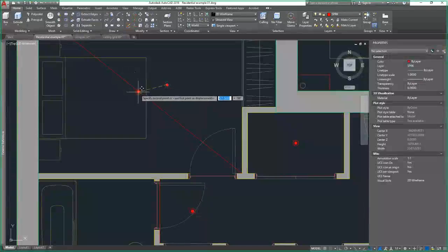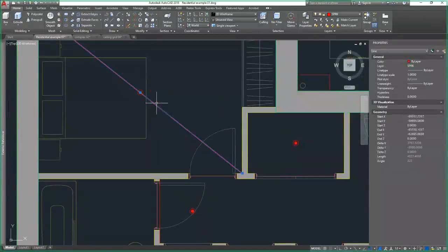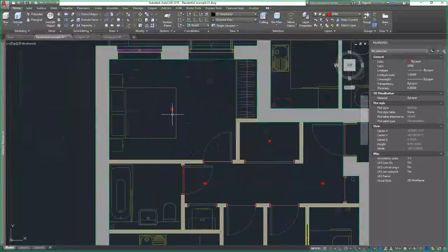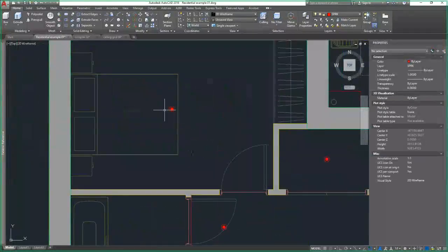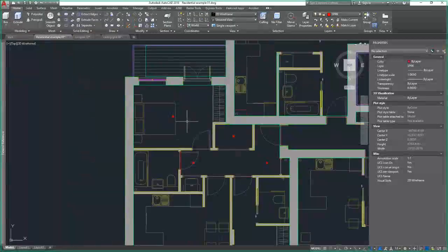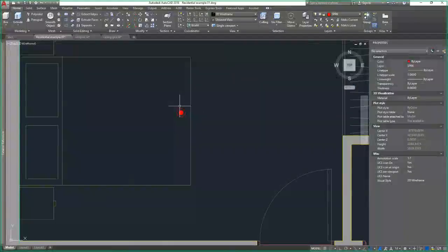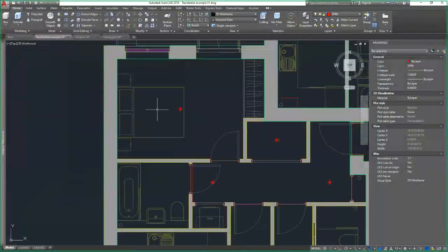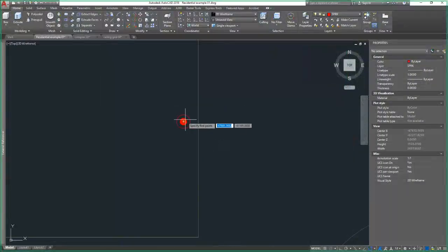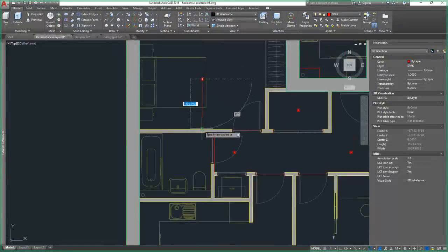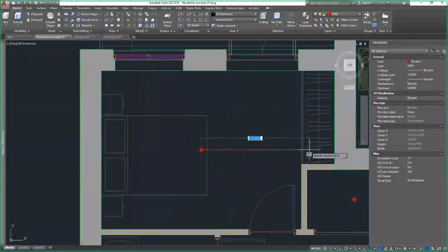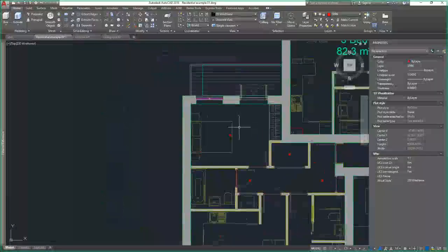It might be that the person that's in charge of the lighting will say, well, actually, no, I want my lighting unit to go in the middle. In which case, we can move it around. We may well then have to switch to 2 heads. If we can't have our head in the middle of the room, then we may well have to have 2 heads to compensate for that move. But there you go. The head's placed in the middle, and we can just double check that. So it's 1.5, 1.8, 1.5, 1.8. So yeah, everything checks out. One head as a minimum, of course, in that bedroom.